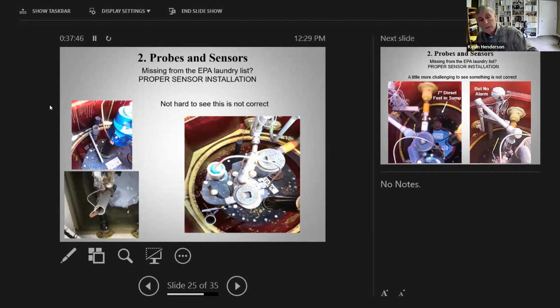The guy in the top left picture wasn't quite sophisticated. He did not have a pipe hanger on the 208 sensor, so he just simply picked it up out of the pipe and stood it up next to it on the lip of the manhole. Same thing with the one on the right. He just picked it up out of the pipe, set it on top of the manhole, to get it up out of the water. So this really has been an ongoing issue for many years. It's nothing new here, and it will continue to be a battle that we have, getting these sensors installed correctly and not having them tampered with.